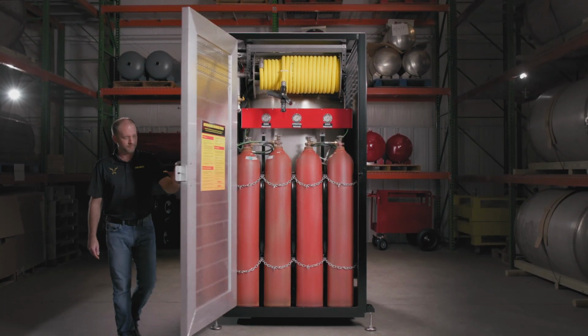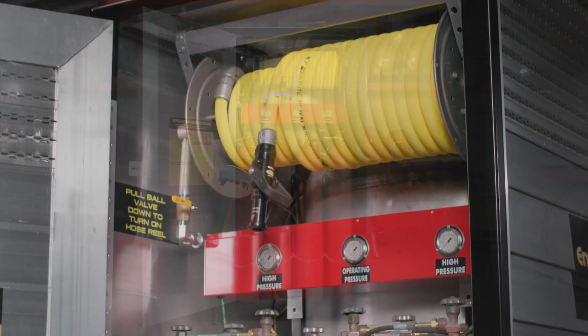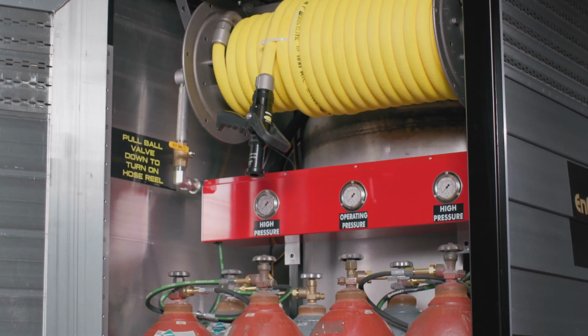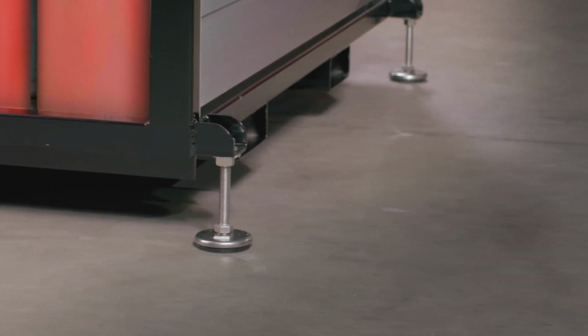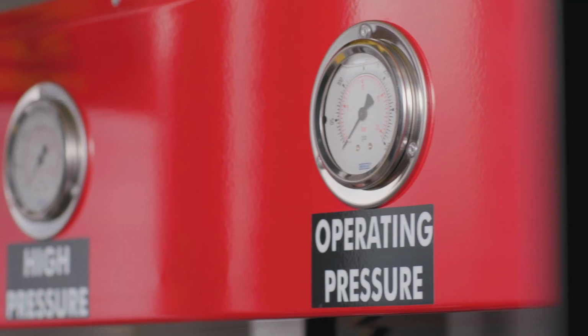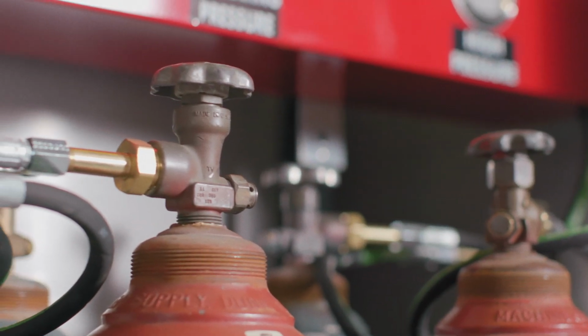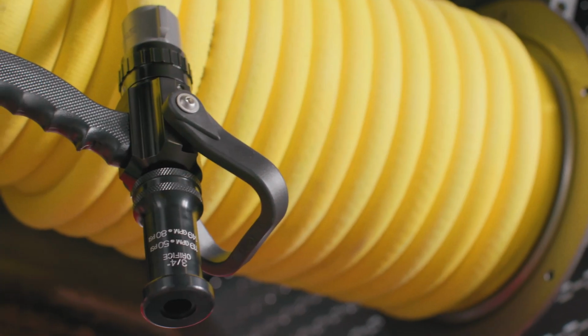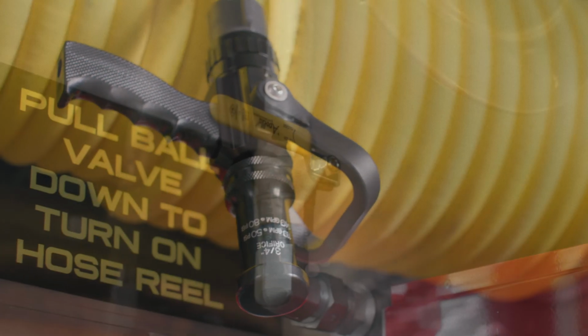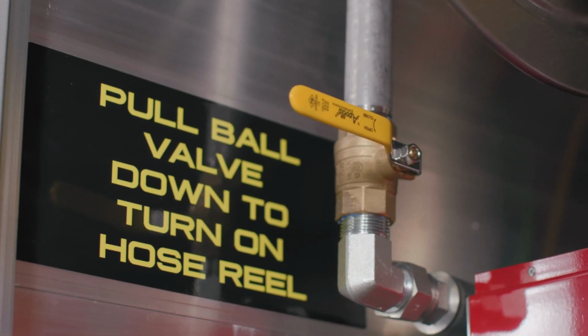The Enforcer 500 system is a fully automated rapid fire detection and suppression system designed for power transformers and other large-scale systems with a potential for fire. Each system contains nitrogen cylinders that charge the firefighting mixture and deploy upon detection of fire by infrared and UV sensors placed strategically at the perimeter of the transformer substations.